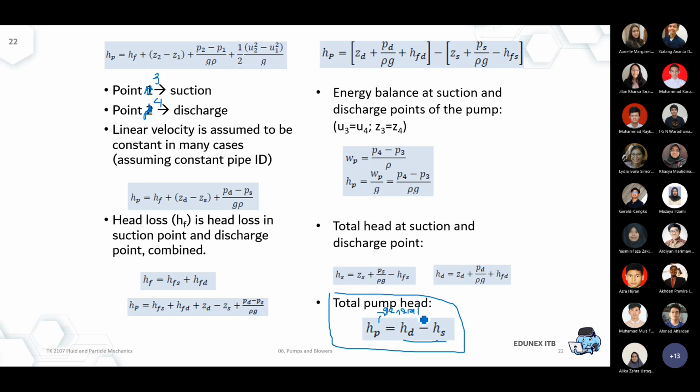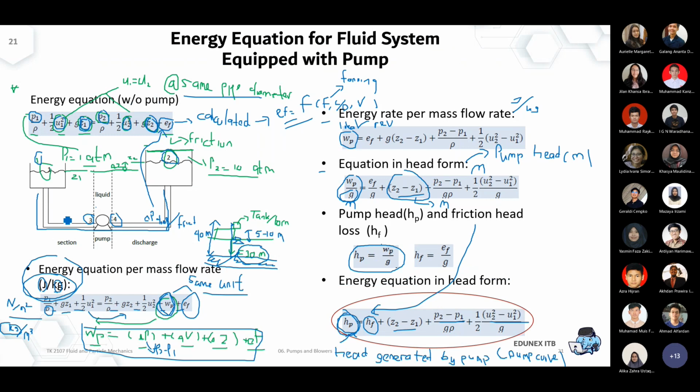So again, be aware of the boundary. Maybe that's the keyword: be aware of the boundary. When you're talking about the delta head of your pump by your impeller, previously in your pump curve, you're just comparing 3 and 4. You're just comparing strictly the entrance point of the pump to the exit point of the pump. But don't forget about what happens in between the source and the destination.